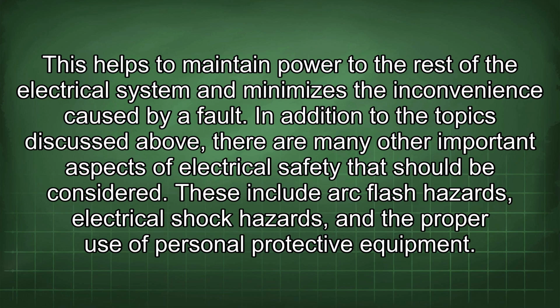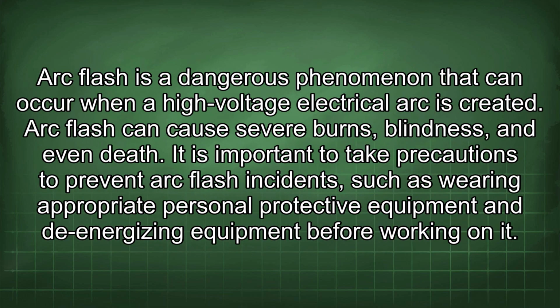In addition to the topics discussed above, there are many other important aspects of electrical safety that should be considered. These include arc flash hazards, electrical shock hazards, and the proper use of personal protective equipment. Arc flash is a dangerous phenomenon that can occur when a high-voltage electrical arc is created. Arc flash can cause severe burns, blindness, and even death. It is important to take precautions to prevent arc flash incidents, such as wearing appropriate personal protective equipment and de-energizing equipment before working on it.